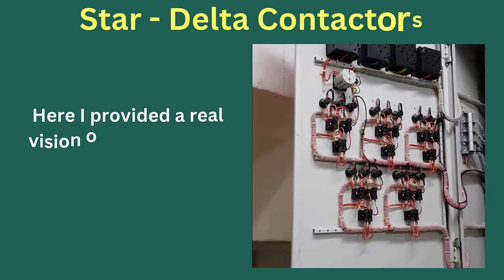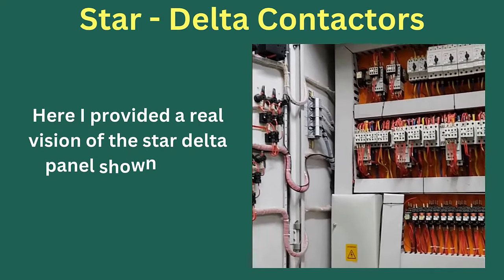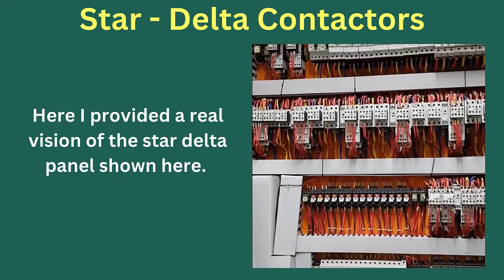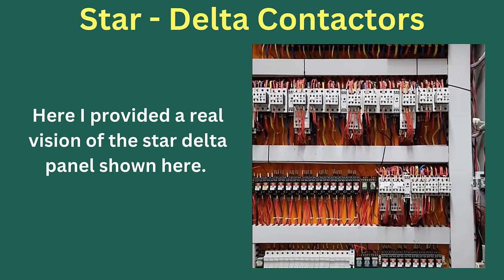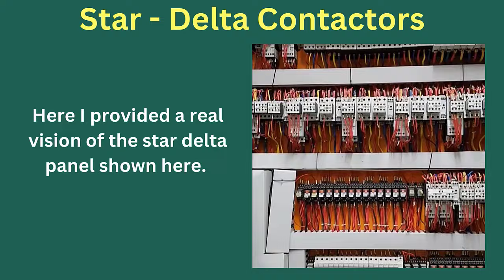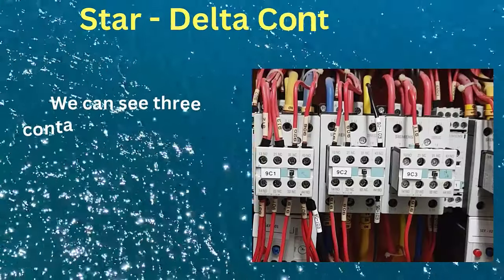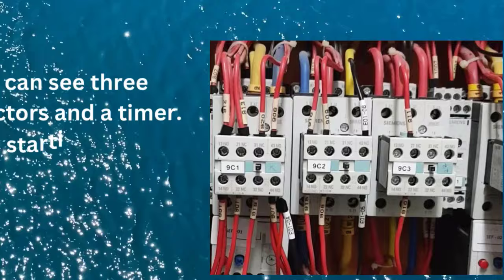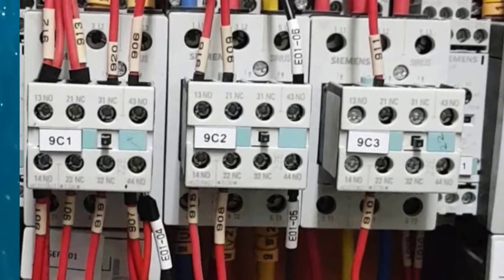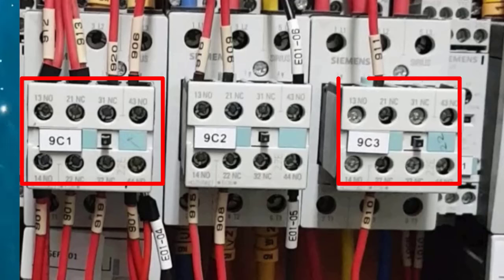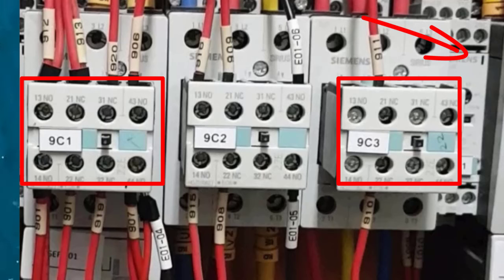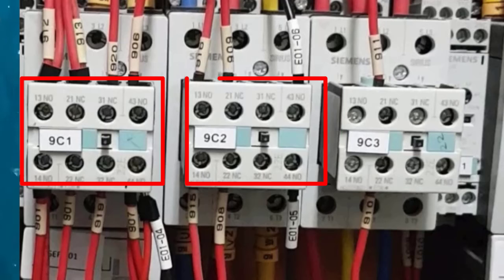Here is a real view of the star-delta panel. We can see three contactors and a timer. At the starting stage, contactors C1 and C3 close, and at the same time timer T1 is also energized. After a specified time, the timer activates: C2 closes and C3 releases. C1 is the permanent contactor.